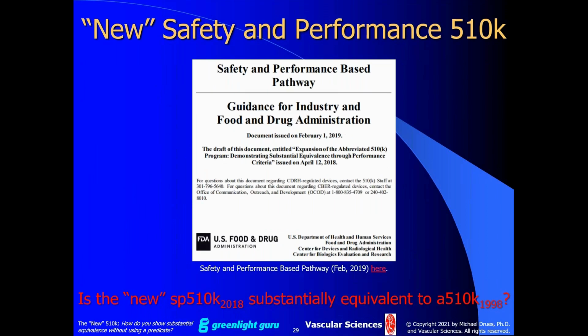So just a couple of years ago, just before the beginning of the pandemic, I think, FDA put out this guidance on the new safety and performance-based 510K, which I would argue, as we're going to continue here, is essentially very similar, if not substantially equivalent, to the abbreviated 510K that was created about 20 years ago.